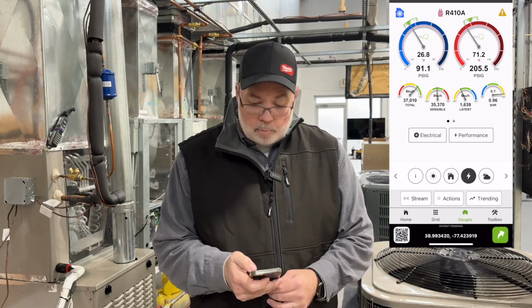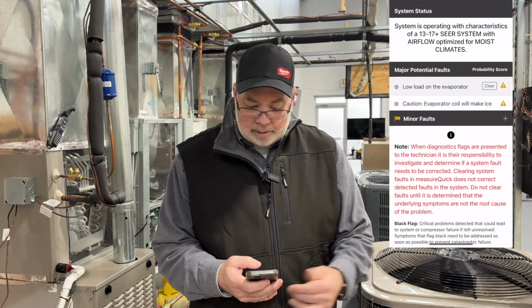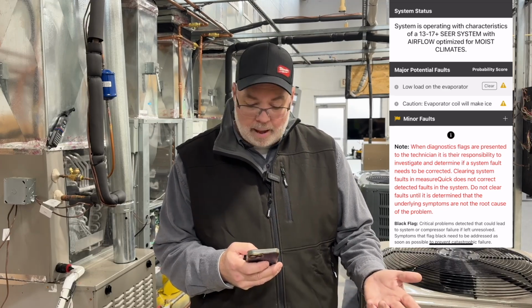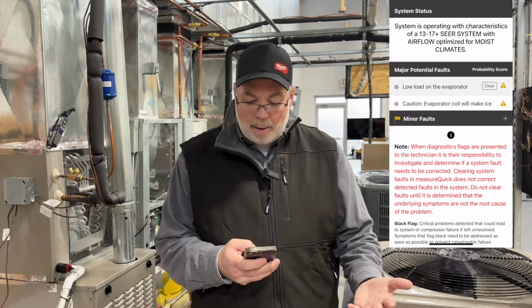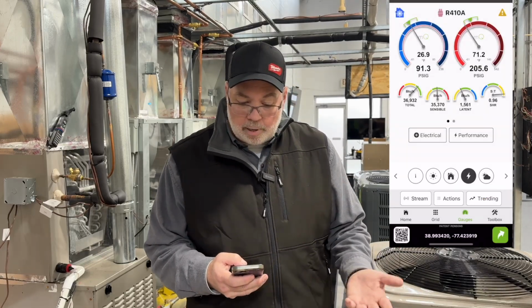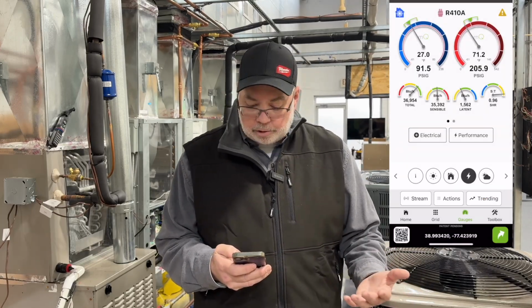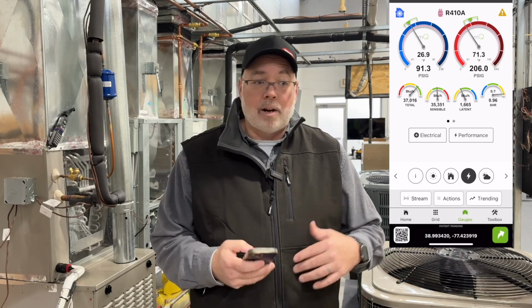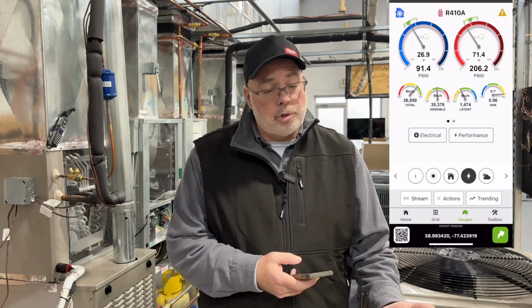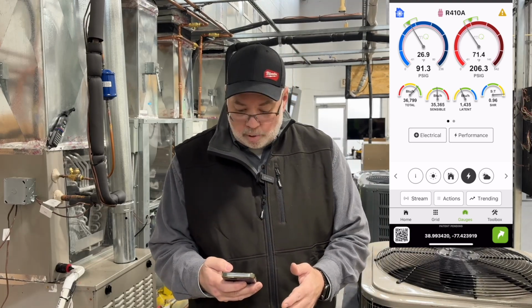At the top right, you'll see it's got a warning, telling us we have a low load on the evaporator, and that the evaporator coil might make ice based on those temperatures. MeasureQuick does an amazing job at this, and all of the JB Climate Class tools will connect. Even the 4-way manifold will connect to both the JB Go V2 app as well as the MeasureQuick app.